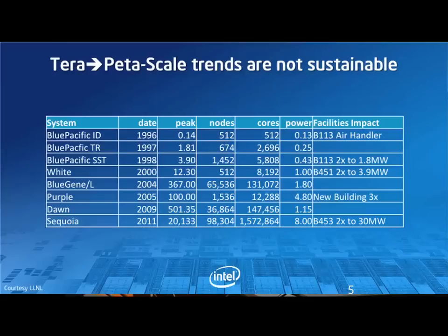We had to refurbish the old NERSC facility at Livermore after NERSC moved to Berkeley, and in doing that, we doubled the power in that building to almost 3.9 megawatts, at a cost of about $17.5 million, and also added 50% more floor space. And then we figured out about the time that we were doing that upgrade that, oh, by the way, it wouldn't handle the next machine, and that building couldn't be upgraded anymore either. So the first 2 buildings were out of gas.